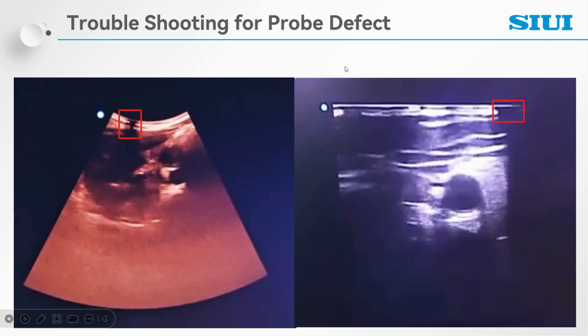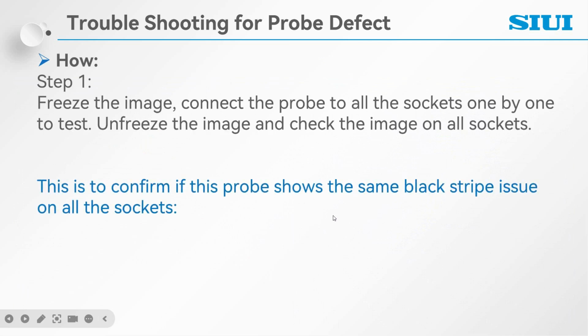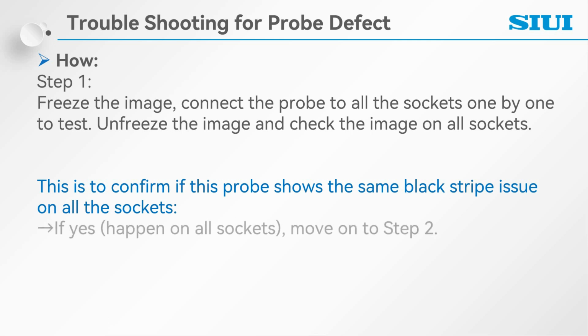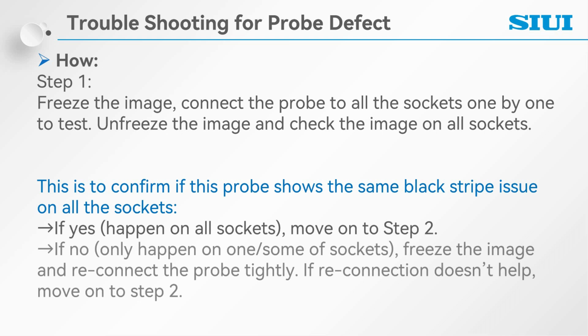So for such a black stripe image issue, let's see the detailed steps of troubleshooting. Step 1. Freeze the image and connect this probe to all the probe sockets on the ultrasound system one by one to test. Unfreeze the image and then check its image on all sockets. This step is to check if this probe shows the same black stripe issue on all the sockets. If yes, that is, it happens on all sockets, let's move on to step 2. And if no, that means it only happens in one or some of the sockets. So this might be a connection issue. Freeze the image and then reconnect the probe tightly. If the reconnection doesn't help, also move on to step 2.